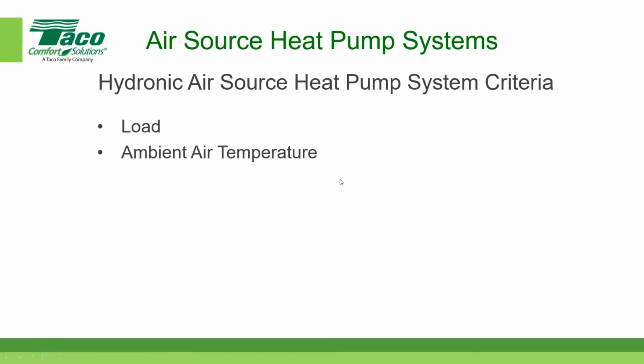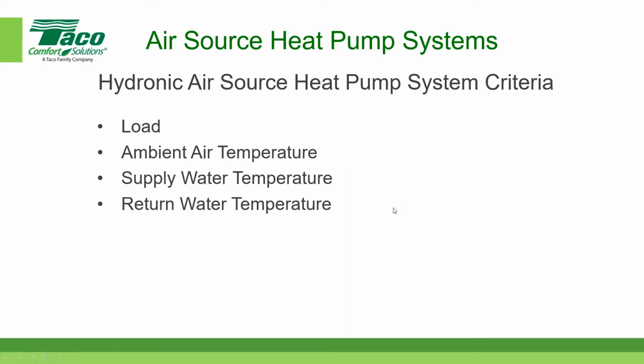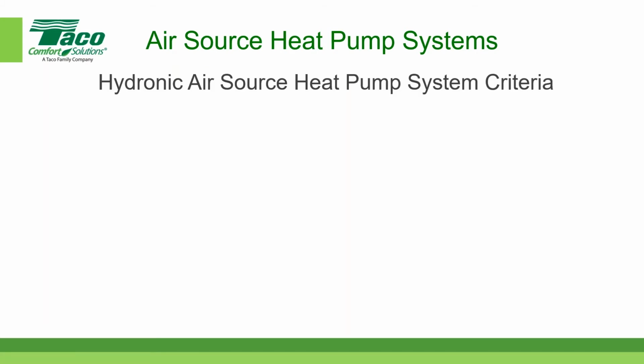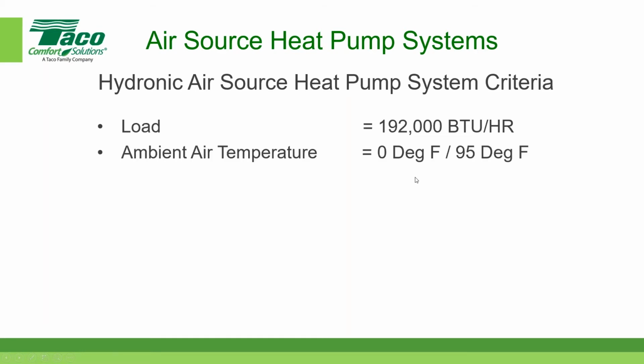Okay. So we also need to know the ambient air temperature. In our case, we're interested in both heating and cooling: the supply water temperature that we're sending out to the system, the return water temperature, the fluid, and the flow in gallons per minute. So what does that look like? Well, in our case, I have a building that needs 192,000 BTUs per hour. I have an ambient air temperature of 0 degrees Fahrenheit for the winter, 95 degrees Fahrenheit for the summer.